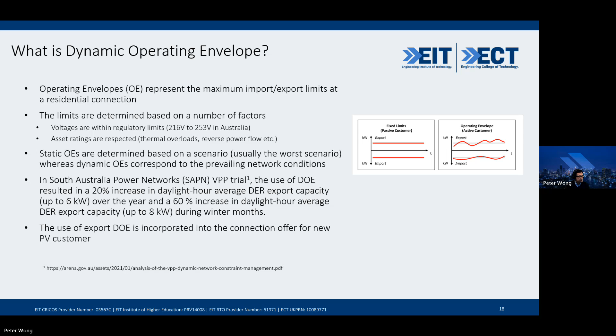You obviously need to calculate the DOE. OPF is one of the commonly used algorithms to calculate it. You need a communication link between the DNSP, the distribution network service provider, and the DER — which in some cases might not go directly to the rooftop PV, but through an aggregator, who then has control over the individual DER. So you need a communication system to convey that dynamic operating envelope to the devices that ultimately need to be controlled.